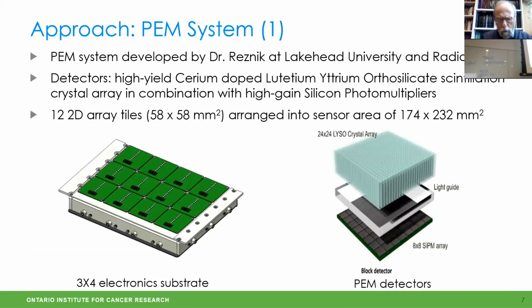So just to review a little bit about the PEM system, because of course it's central to this project. It's, as I said, developed by Radialis, a company out of Thunder Bay. So it is based on some new technologies. The detectors are high-yield cerium-doped lutetium yttrium orthosilicate scintillators. You see the picture on the right-hand side. It's an array of crystals that have a very high detection efficiency for the annihilation radiation in PEM systems, and then coupled through a light guide to a detector array.